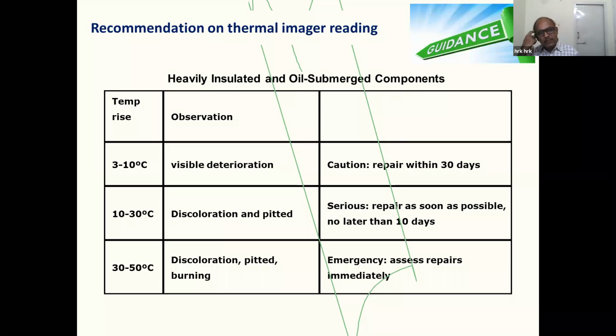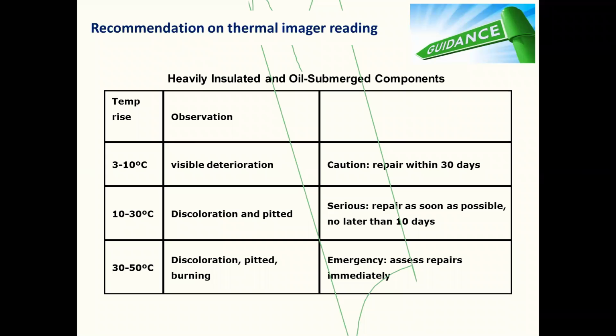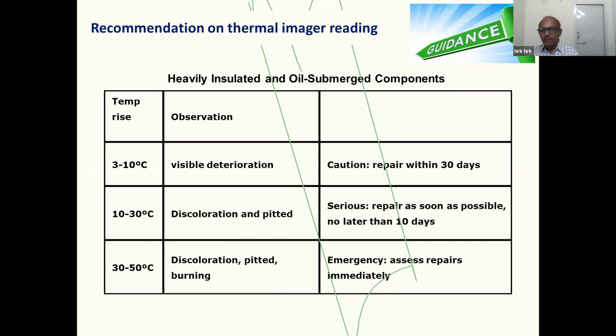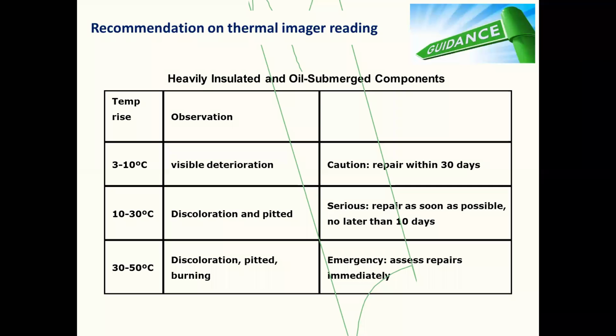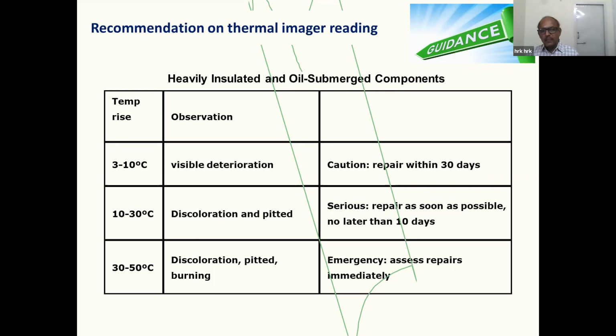For oil-immersed components like transformer windings, if there is a 3 to 10 degree rise, they have cooling fins to circulate the oil and keep the normal temperature. If there is a 3 to 10 degree change, you can repair within 30 days. If there is more than a 10 degree change, the cooling is not effective and there may be a potential failure, so we have to act at the earliest, within 10 days. If a 30 to 50 degree change appears, there is no cooling at all, because the oil is not properly circulated or the oil is degraded, or for many other reasons. Then we have to take immediate corrective action.